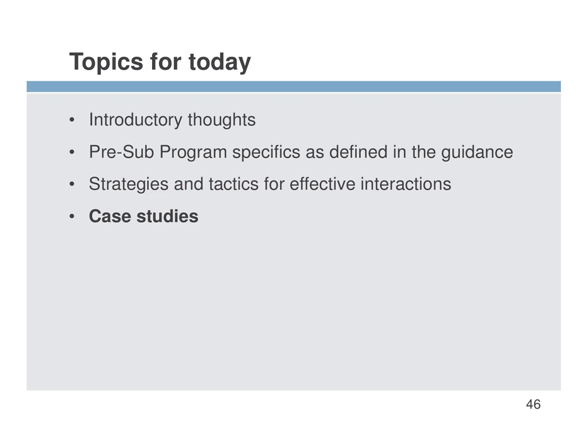Sometimes at the end of the pre-sub, FDA is giving you advice, you don't like it. You'll come back and say, this is what we think should be done, and FDA says, well, we have an area of disagreement. So there's another point on minutes. Minutes can certainly reflect we agree to disagree on this point, and sometimes we can agree to disagree on what was said in the meeting. And so at that point you say, can we keep this pre-sub open, and then you'll come back to it. At some point they will say, perhaps, we feel this pre-sub is closed. Practically speaking, it doesn't make a whole lot of difference except that you'll have to wait another 90 days.